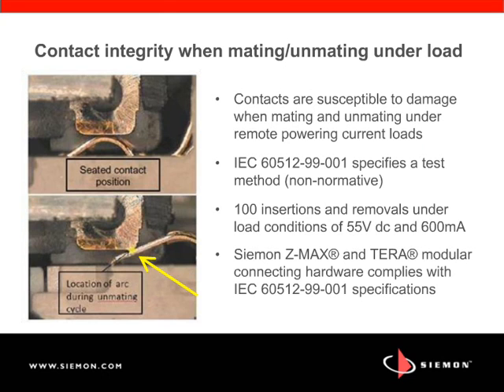It's IEC 60512-99-001, which was specifically developed to ensure reliable connections for remote powering applications deployed over balanced twisted pair cabling. So the first thing we've learned here today is that when specifying cabling systems supporting high current remote powering applications, ensure that you're selecting and specifying connecting hardware whose contacts have been designed in such a way that this arcing occurs in a different position from the final seated contact position.